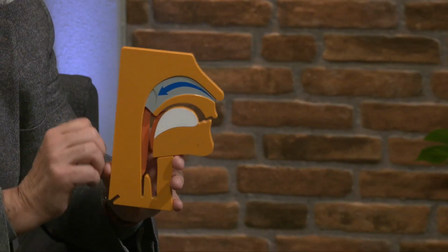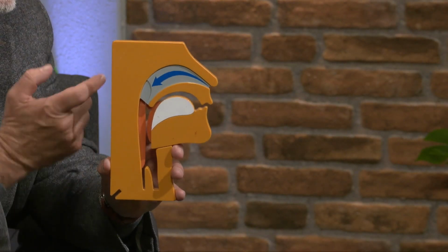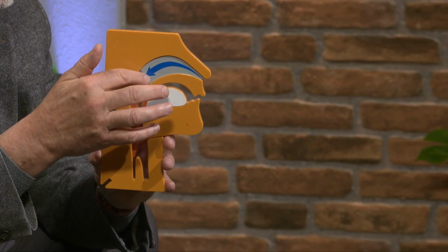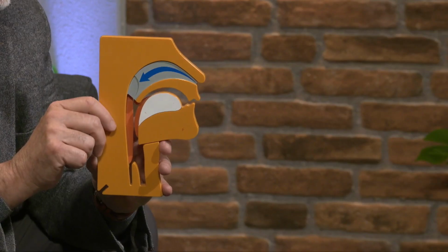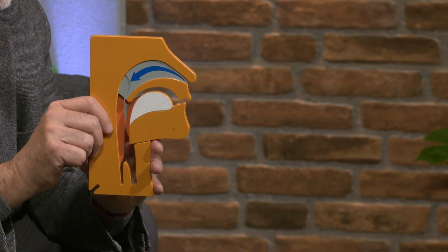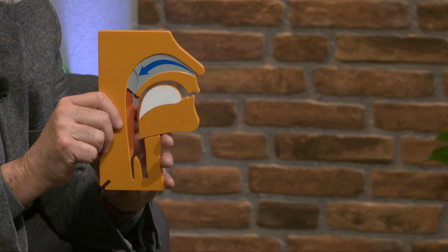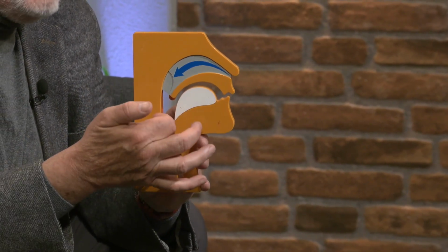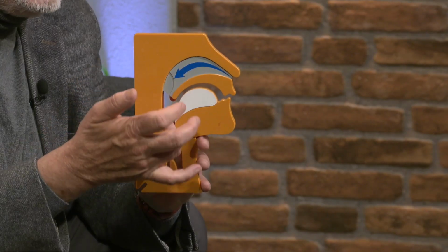Okay, so I've turned the machine off again, but I want to show you how this all works. And we can see that here on the model. I've turned the model around now, so you're seeing the backside. We're essentially pumping air in through this path, normal air. The CPAP doesn't supply oxygen, as some people believe, just air. And with that air, we're basically pushing this whole thing open. And that allows air to flow through here again.